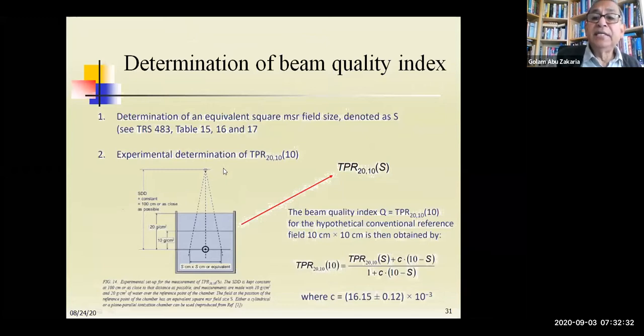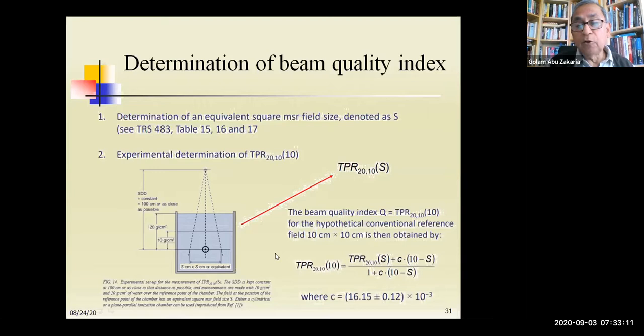Here is the determination of the beam quality index. Everybody knows how to determine the Q, or actually TPR 20,10, from the 10 by 10 field. You know, everybody. This is actually here. But how should we transfer from the small field to this value? How can we do that? This S is actually the equivalent square field of the MRS field. That means in an MRS field of 10 by 6 maybe, you can first calculate the equivalent quadratic field and then go to this relation, where you have the measured value for the small field and calculate it in TPR 20,10 in the 10 by 10 field, and this can be used to get the values of correction.